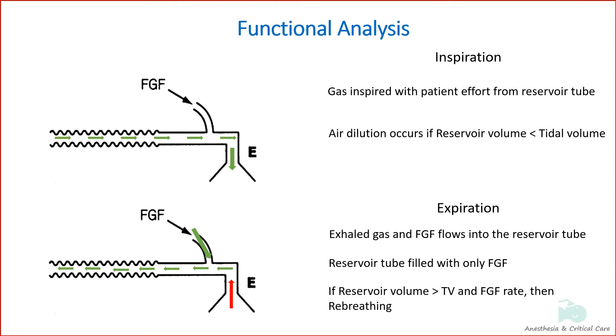If the reservoir limb capacity is more than the tidal volume of the patient and fresh gas flow is less, re-breathing can occur.